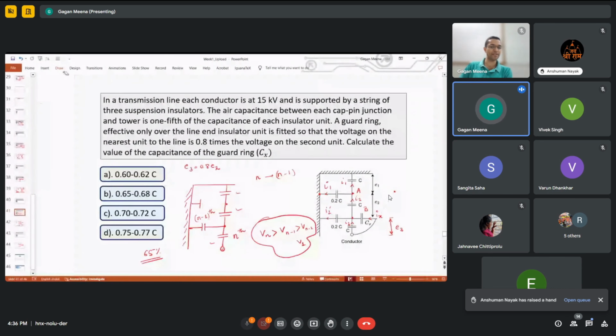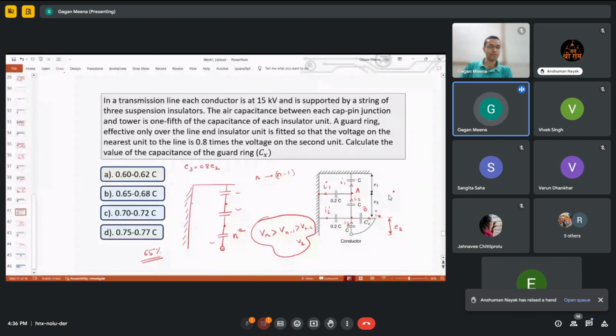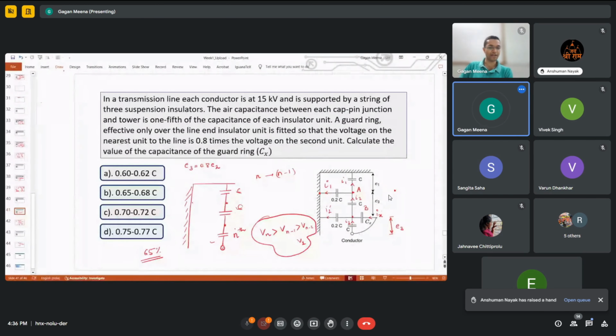If we remove these capacitances, and all these capacitances are identical, then what will be the voltage? The voltage across these capacitors will be same. They are connected in series, so they will share equal voltage. Let's say the phase voltage is Vp, then the voltage across each capacitor will be Vp by N. So let's say if this is 30 kV, then the voltage across each capacitor will be 10 kV each, if there are no stray capacitances.